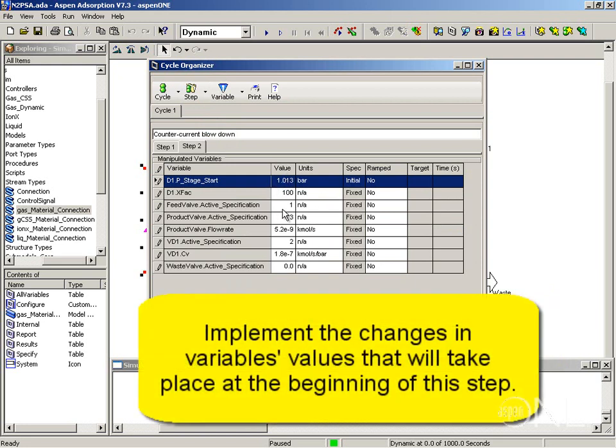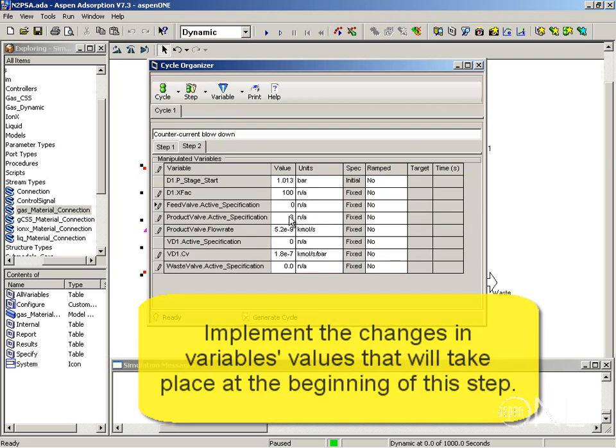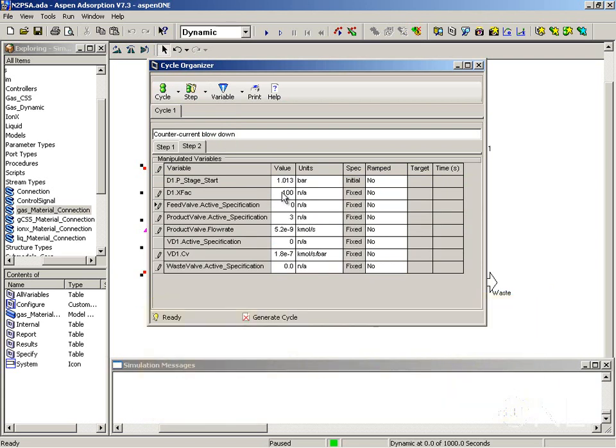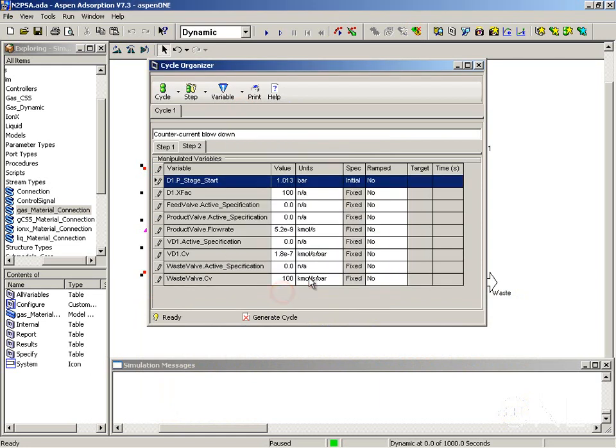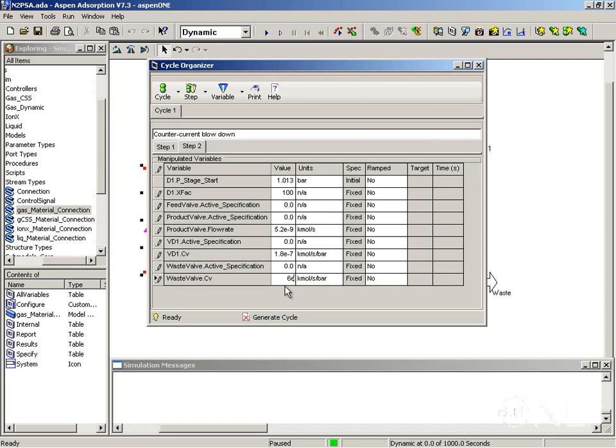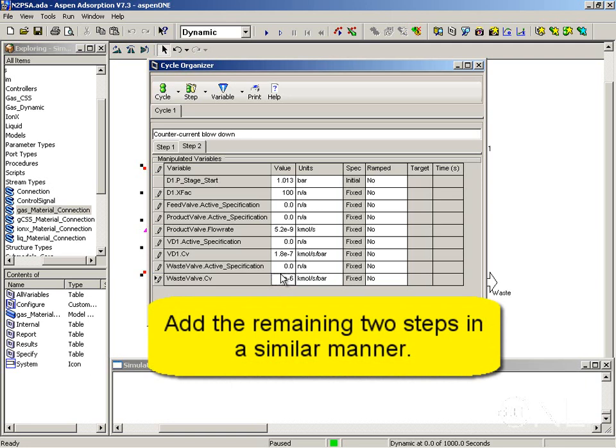And now I want to make the following changes. So the changes in values I am going to do here will happen as soon as this step starts. I want to close valve VD1. I want to close the feed valve. I want to close the product valve. And I want to open the waste valve with an active specification of 2 which is the CV. I need to find the waste valve CV, add it here, give it the value of 6E minus 6.